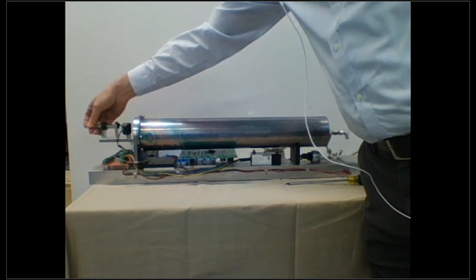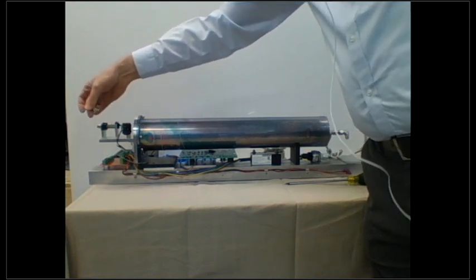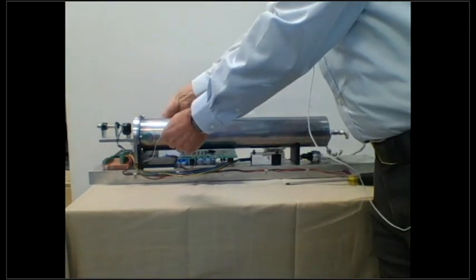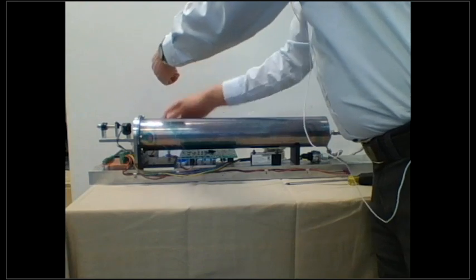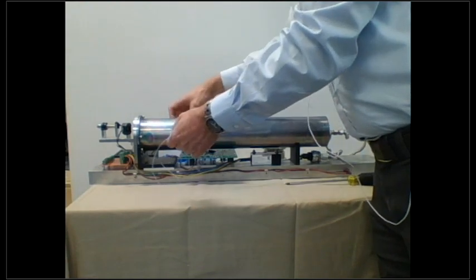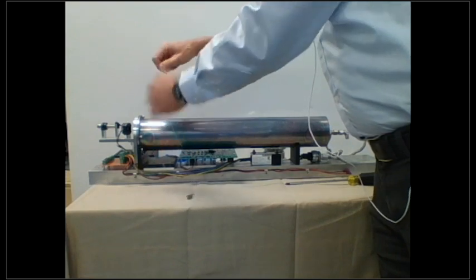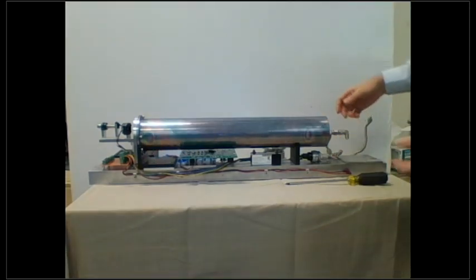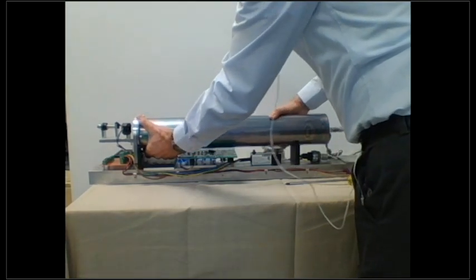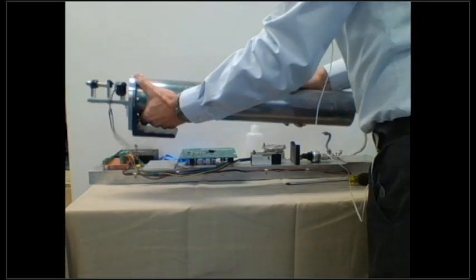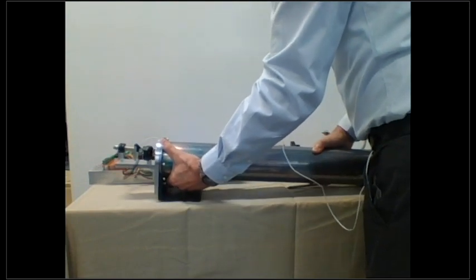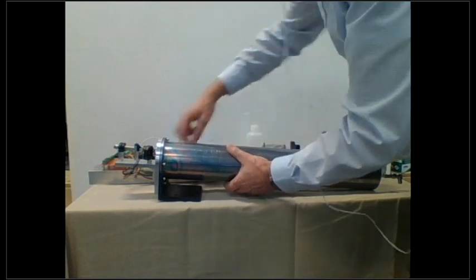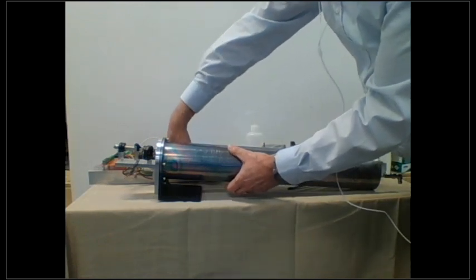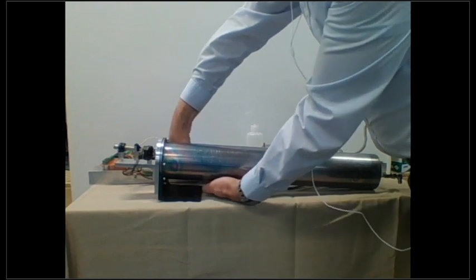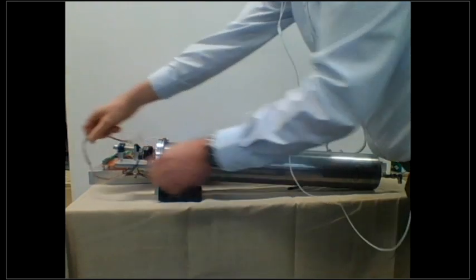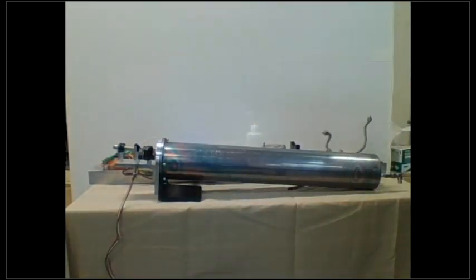So it just screws out and you can just pull it out. It's keyed, so you can't put it back together wrong. And to manage the fiber, we just simply wrap it around the cell just to keep it from flopping around when we're taking the cell in and out. But it can be just simply removed and gotten out of the way. And then, as long as all the fittings are undone, the entire cell assembly will just lift off just like this. And you can set that aside. I should also mention that there's an electrical connection here from the detector to the main board, so don't go too far without undoing that first.